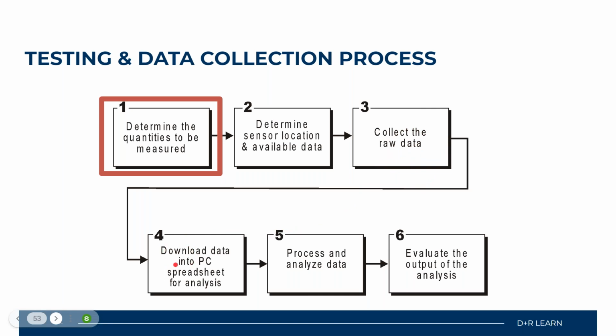And then we go to step 4, which we briefly touched on, but the data that's picked up is then processed and analyzed for any type of audits, troubleshooting, or if you have some sort of repetitive issue. So if you have a chiller that is surging every evening or in the middle of the night at 3:30 in the morning, and it does that for a whole week, and you're wondering why operation is sluggish or something is wrong, you're able to go back through the records and look at that, because there's no one on site at 3 in the morning watching that chiller in operation, because not every site has the ability to do that. What they rely on is the ability to monitor these different systems through the use of remote technicians that are actually able to watch their systems in operation.